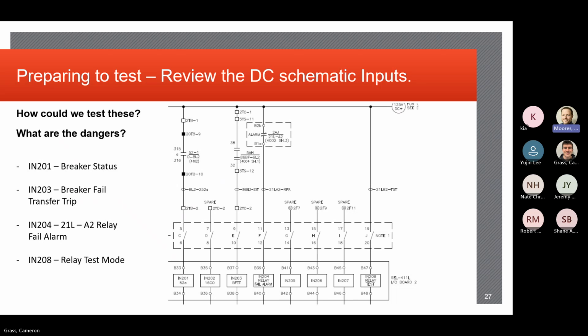And these relays have a lot of logic and settings built into them. You need to understand the applications like we talked about last week. There's software that you can plug into these relays and the test sets now, and it'll automate testing for you and manipulate settings and all that, which is great because it makes the test quick and probably can make test companies more profitable, but it's not truly testing the application as it's intended. It's manipulating the test. So I'm not a fan of that. But anyways, that's my soapbox moment.